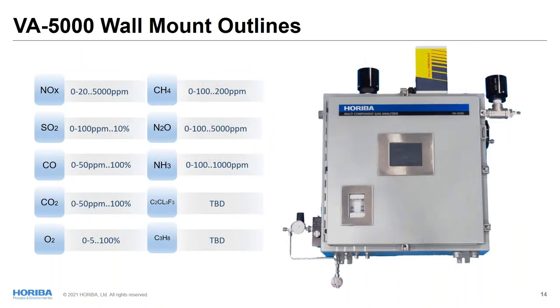Here are the parameters that the VA-5000 can measure. As you can see, NOx can go from 0 to 20 ppm at the lowest range, and up to 5,000 ppm. You can select the NOx measurement from chemiluminescence detection or a conventional NDIR. Methane is measured by NDIR, from 0 to 100 ppm up to 200 ppm. SO2 is from 100 ppm to 10%. N2O is from 100 ppm to 5,000 ppm, and CO is 50 ppm to 100%. Ammonia can go from 100 ppm to 1,000 ppm, and CO2 is from 50 ppm to 100%. O2 is 5% to 100%.